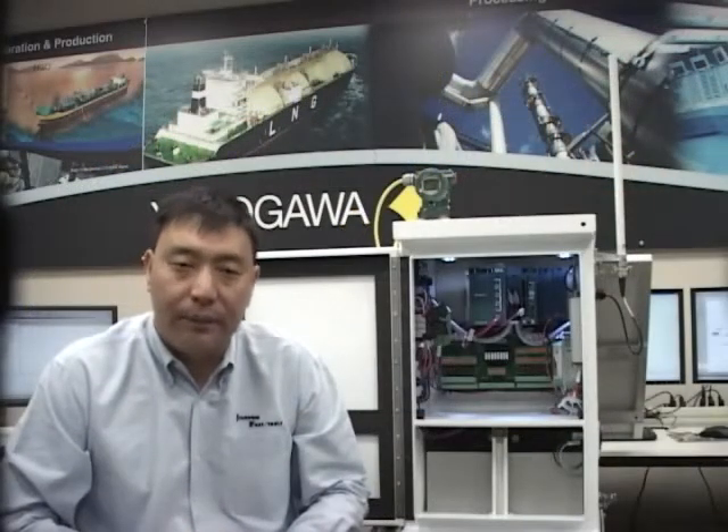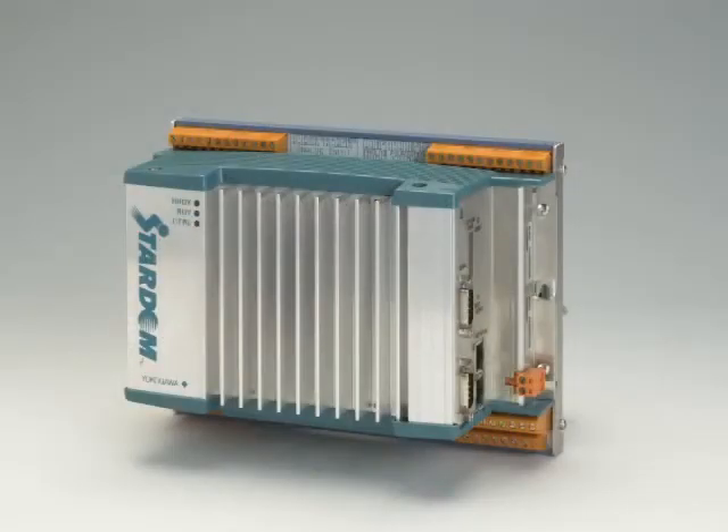Let's take a close look at the STARDOM. First is FCJ. It has two Ethernet ports, which can connect to two different networks or team together as a redundant network connection. It has a fixed number of traditional IOs, two Foundation Fieldbus segments, and two built-in DE-9 ports for serial connections such as Modbus RTU. FCJ is suitable for process applications with a small number of IOs, for example, wellheads.